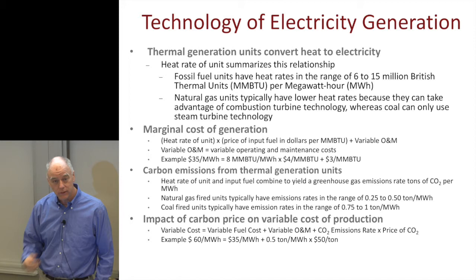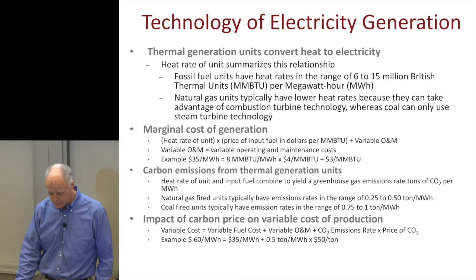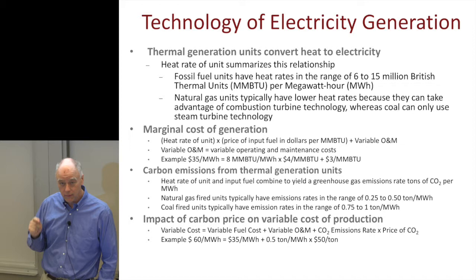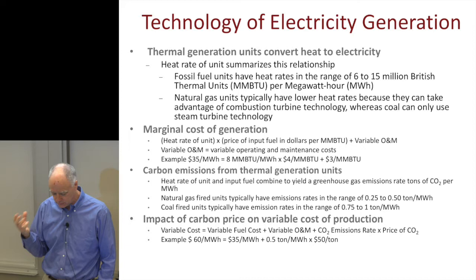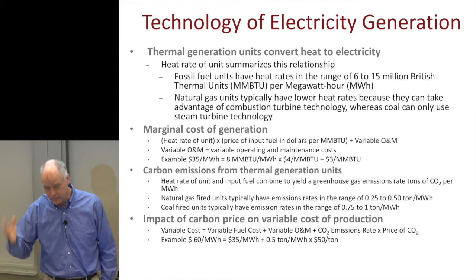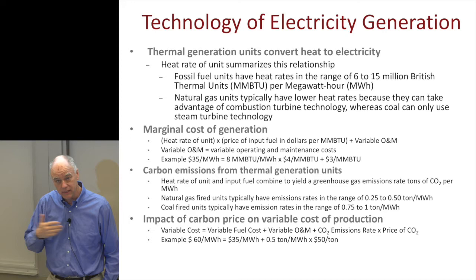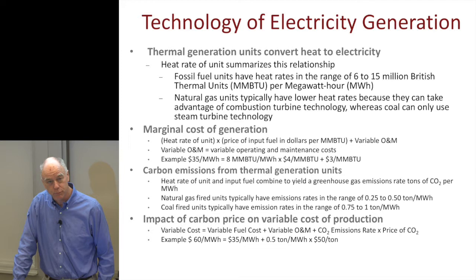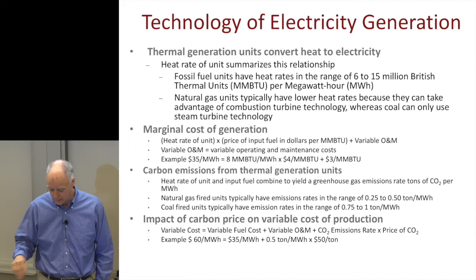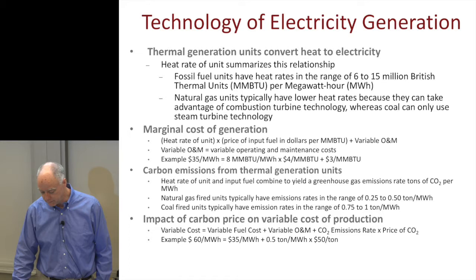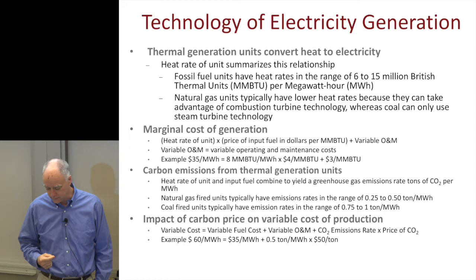Your job as a market participant is to procure the input fuel, then calculate: what price am I paying for fuel, what's my heat rate — multiply those together and you get the variable fuel cost. For example, a combined cycle natural gas unit typically has a heat rate of about six to eight million BTUs per megawatt hour. If you buy natural gas at $4 per million BTU and use a heat rate of 7, you get $28 as your variable fuel cost per megawatt hour.